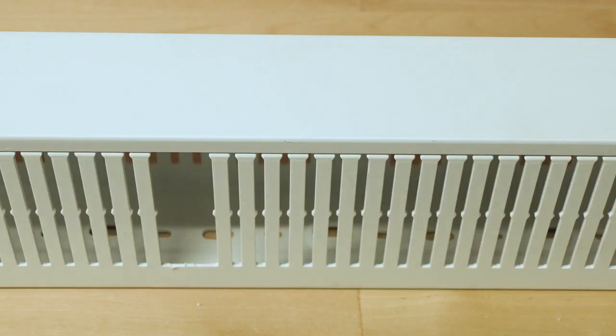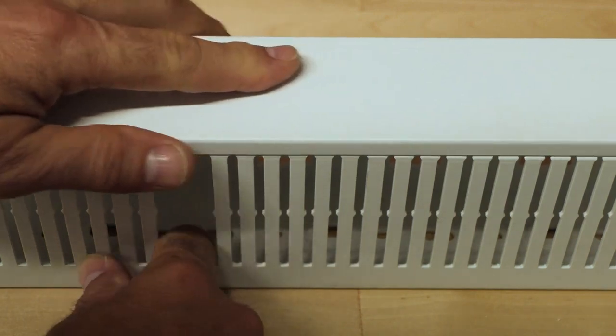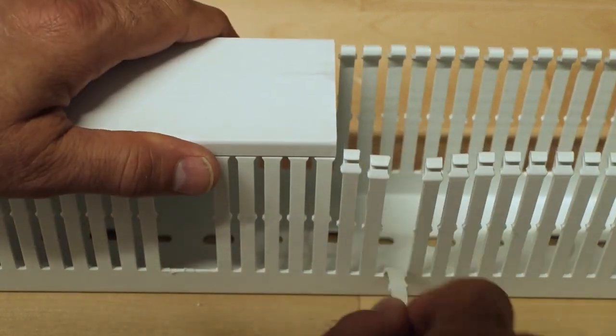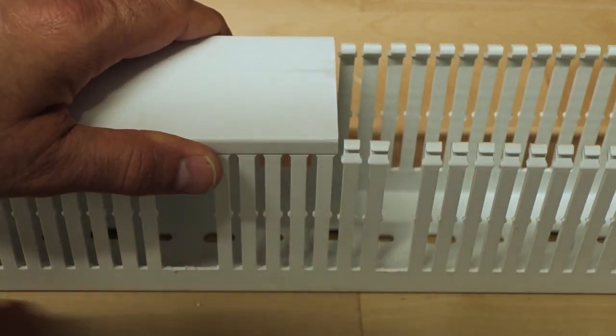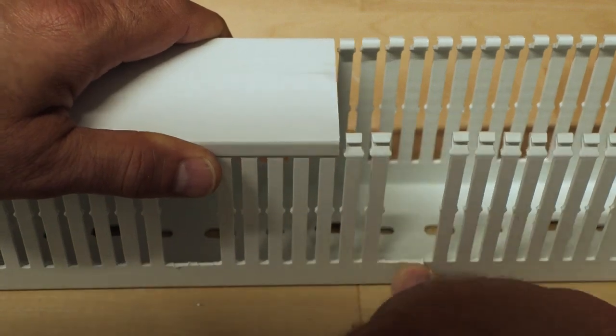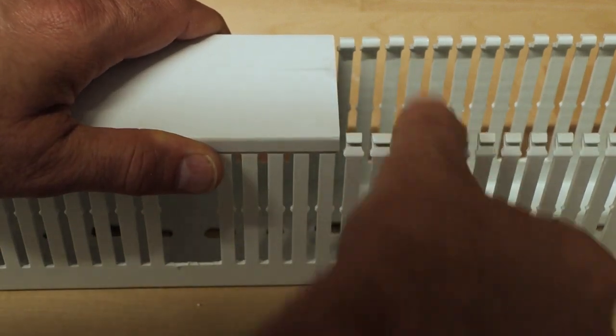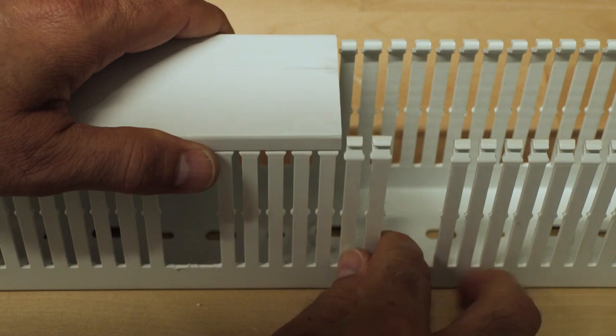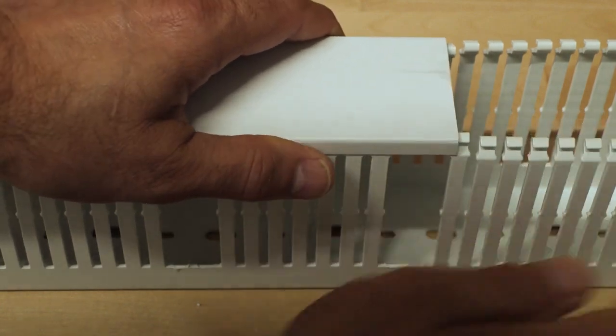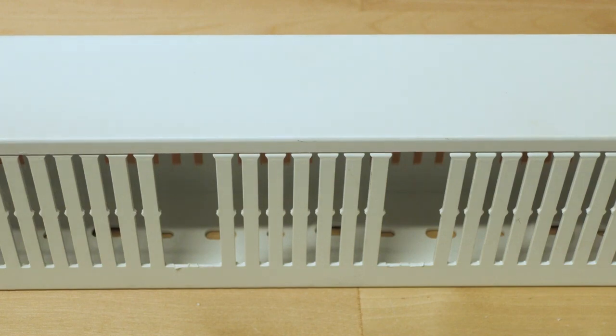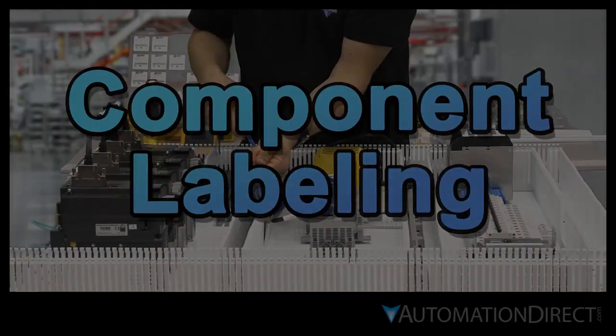As components are installed, you may find that some fingers on your wire duct will get in the way of larger wires or cables. Luckily, wire duct is designed to accommodate this. Simply remove the cover of the wire duct and bend the fingers away from the center of the duct. They're scored from the factory and will cleanly snap free. Be careful with this though. Once a duct finger has been removed, it's off for good.